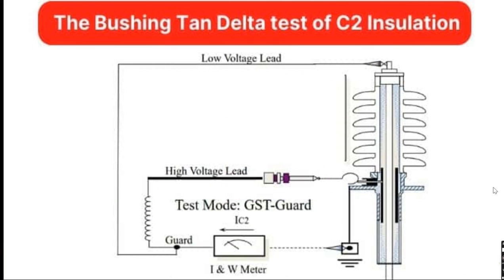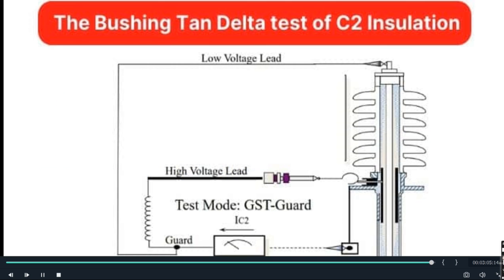For example, for tan delta testing of a transformer bushing to carry out a test of C2 insulation, GSTG mode of testing is used, where the HV terminal of the bushing is connected to the guard terminal of the test kit. Hence, to get accurate test results, the correct mode of testing must be chosen.